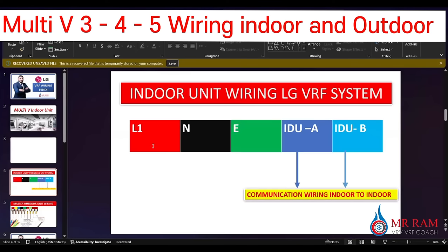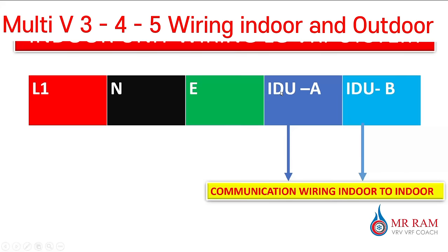When we install any indoor unit, first of all we find out the wiring system: Line 1, Neutral, Earth, and the communication wires IDU-A and IDU-B. This is the circuit for communication wiring. When installing any LG VRF system — Multi-V4, V5, or i-series — the power supply and communication wiring look like this. We have to connect properly and ensure the communication wiring is connected correctly with the same wire code and thickness: 0.5mm² to 1mm² according to system capacity.